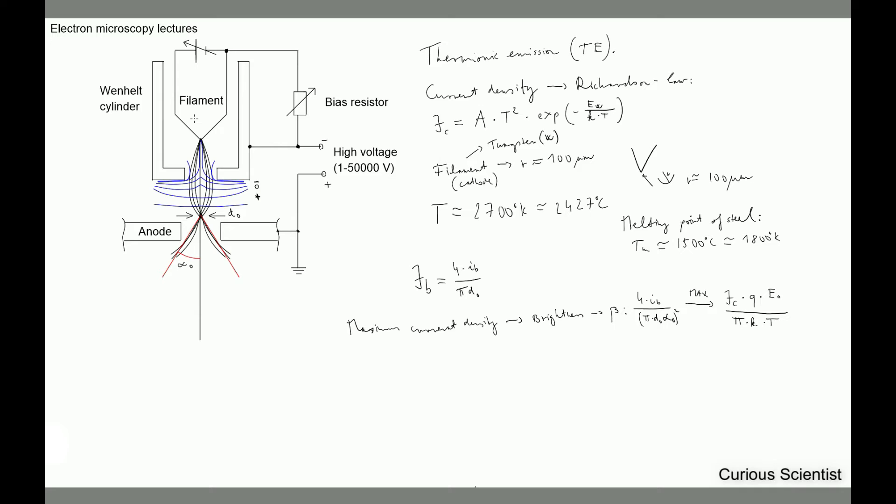We can alter the electrostatic field by changing the distance between the filament and the Wehnelt cylinder, and by changing the variable bias resistor. With these adjustments we can maximize β, the brightness, and find an optimal value. Not all devices allow changing the filament-to-cylinder distance, so that may not be an option, but manufacturers usually optimize this already.